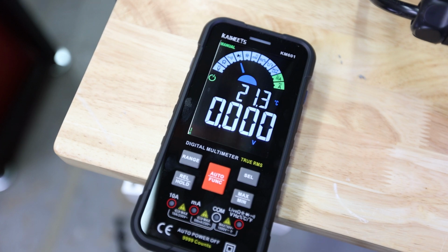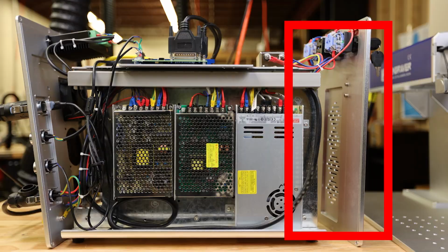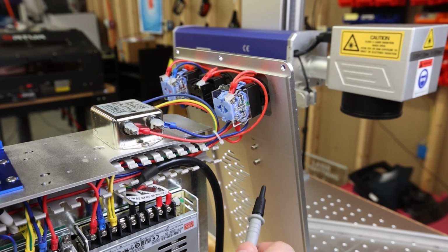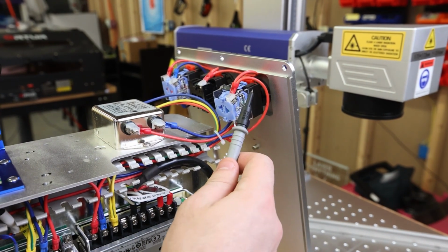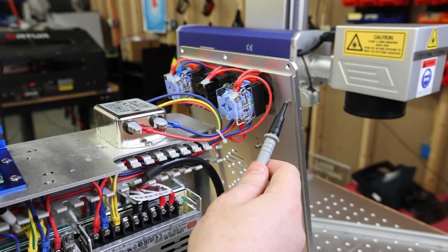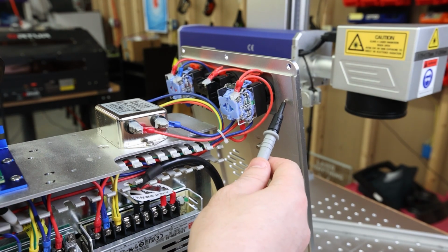Grounding is important because if there is a short somewhere in our machine, we don't want to touch the case or component and get shocked as a result. If your front panel is not making contact with the rest of the machine chassis, it will likely not return a 0 in your continuity test. Touching the front panel to the body of the machine should resolve this, as they're not always grounded with wire.